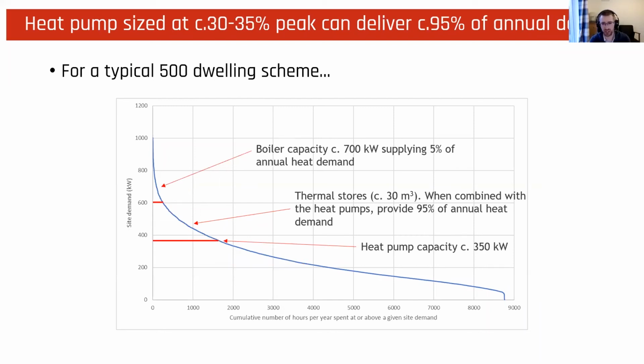I think it also becomes really interesting when you push this boundary to say, well, what if I want to deliver 95% of heat from my heat pump and thermal store system? Actually, you don't need to increase that heat pump capacity all the way up the peak demand curve so that you're installing a megawatt of heat pumps. You can push it up just to 30, 35% of peak demand and increase the thermal store a bit more. For a scheme such as this, you can have a heat pump capacity of 350 kilowatts, so about 35% of peak demand, some large thermal stores, and that circuit on its own could do 95% of that annual heat demand. And then you're only asking your boiler to do 5% of the annual heat demand.